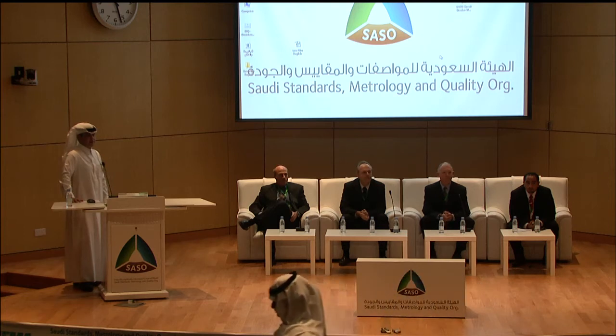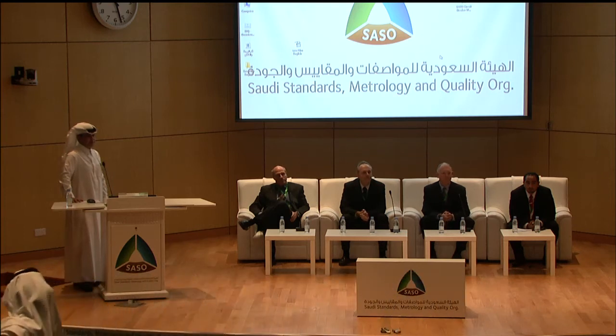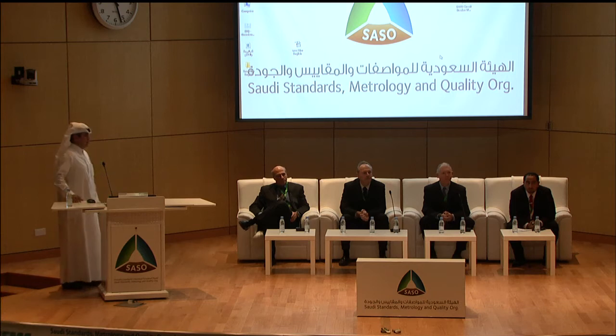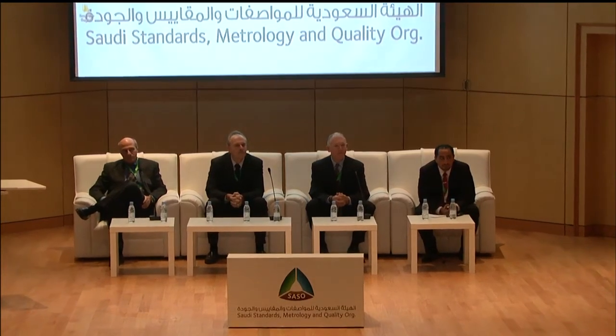Subhi Salame from Alfanar. Yes, for the GFCI breaker, is it now mandatory to have earth leakage, overload and short circuit protection, or is earth leakage enough because it's used as a branch breaker inside the load center? If it doesn't include overload and short circuit, it's a protection only for earth leakage. And this is the first question. The second question: if we connect two or three loads after this RCBO or earth leakage breaker, can it be used or not?